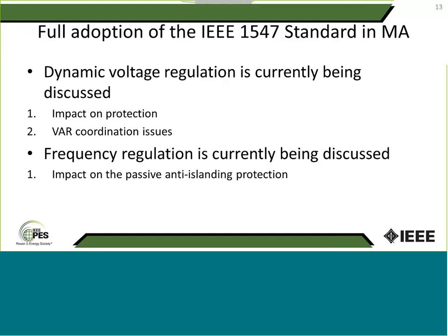island if the frequency regulation is enabled, because once you do have an active power mismatch in the island, which impacts the island frequency, with frequency regulation enabled the DERs will try to regulate the island frequency rather than trip, which is not what we want to see on the distribution side. So this is something that we're also discussing.